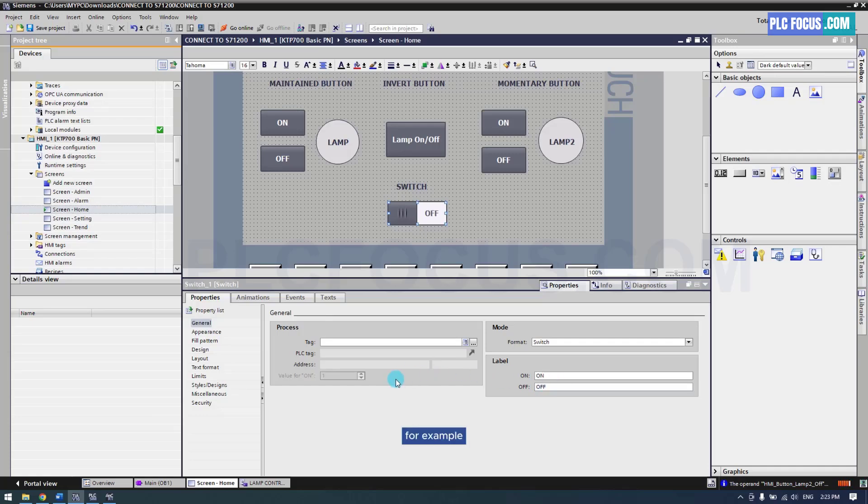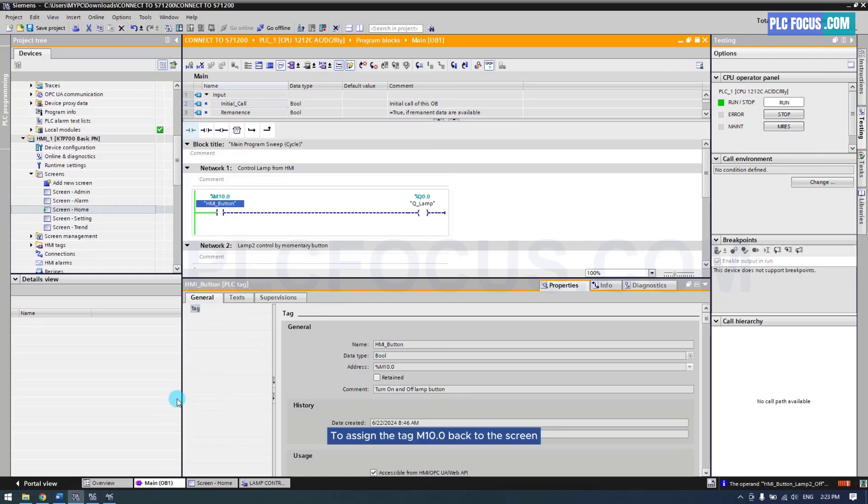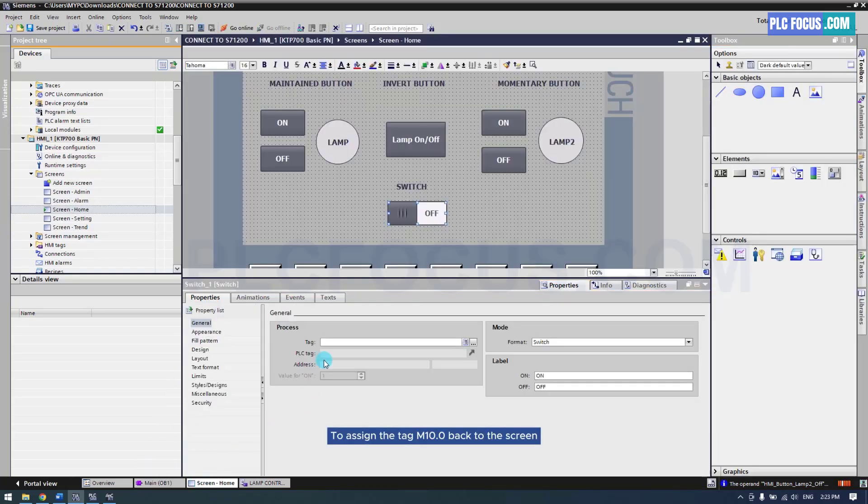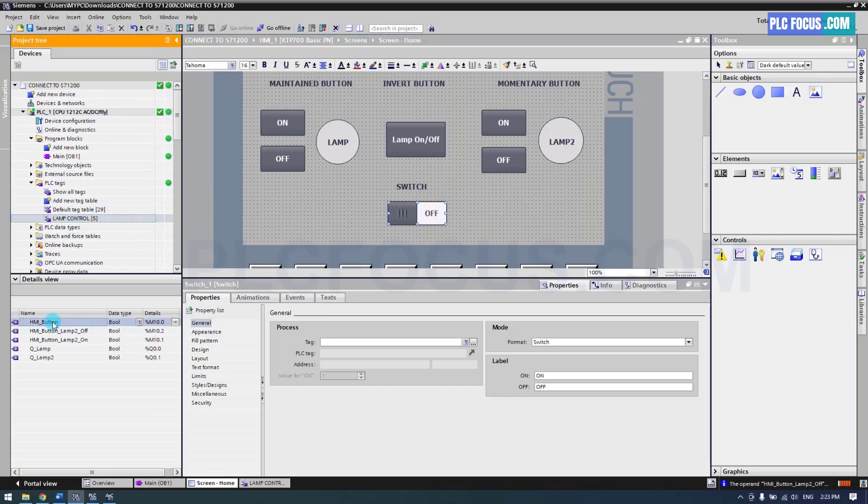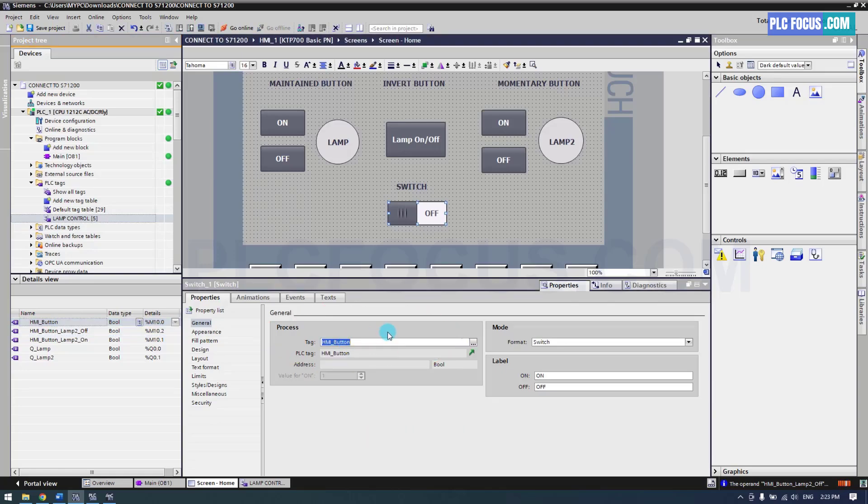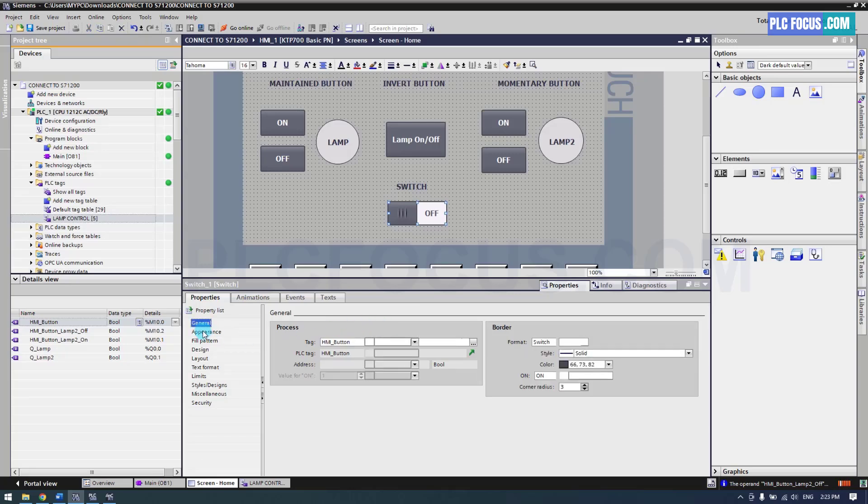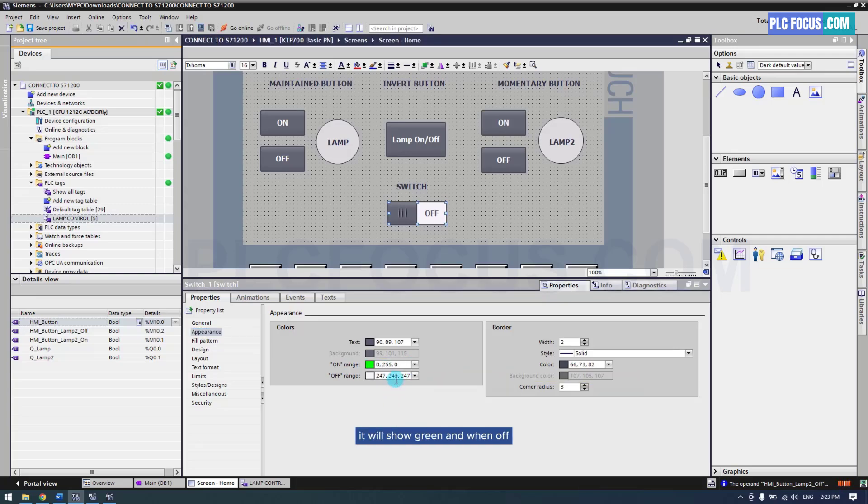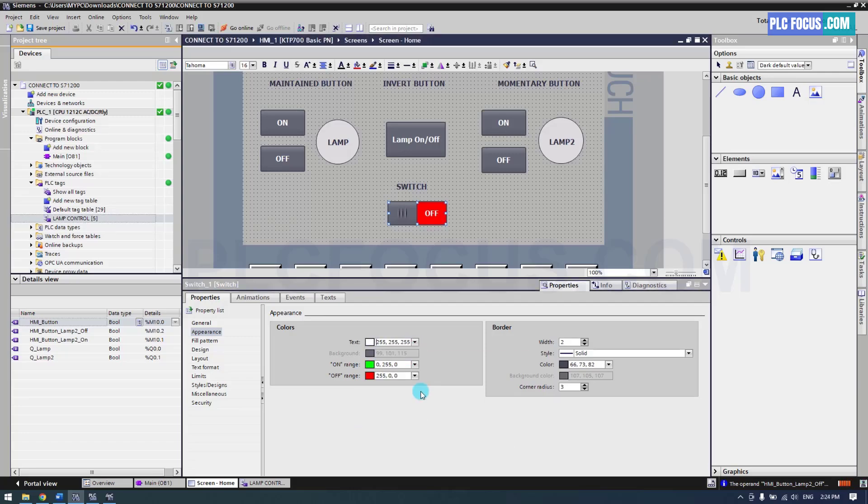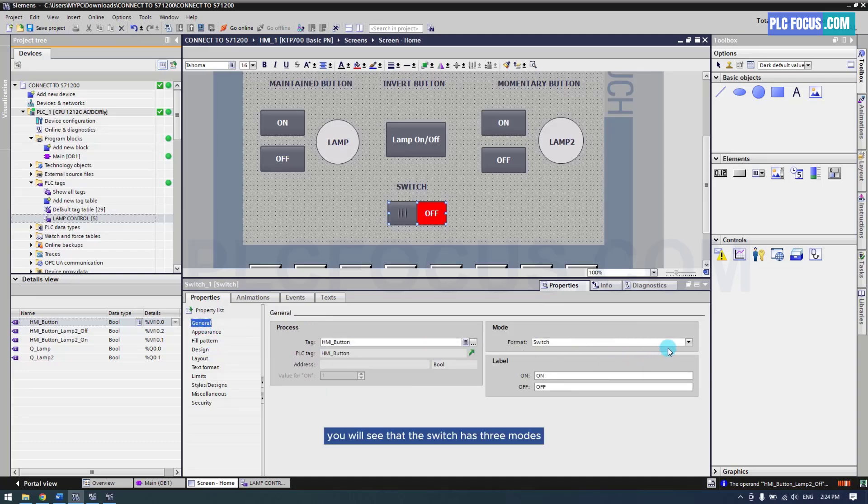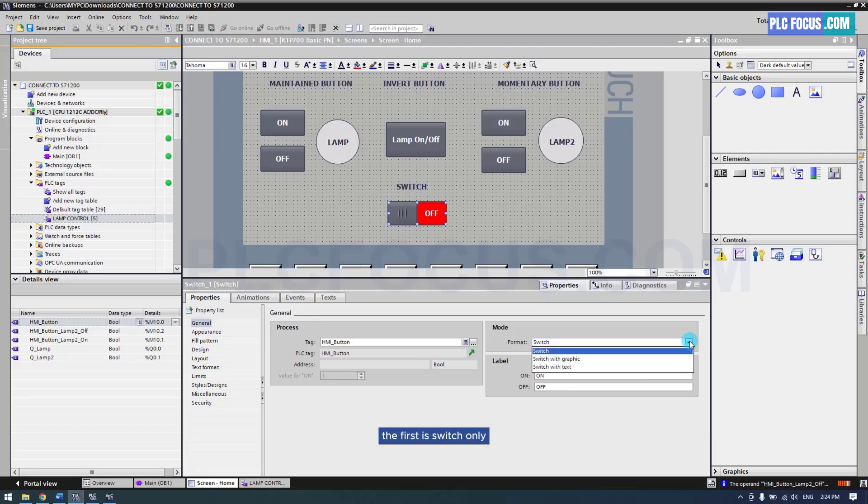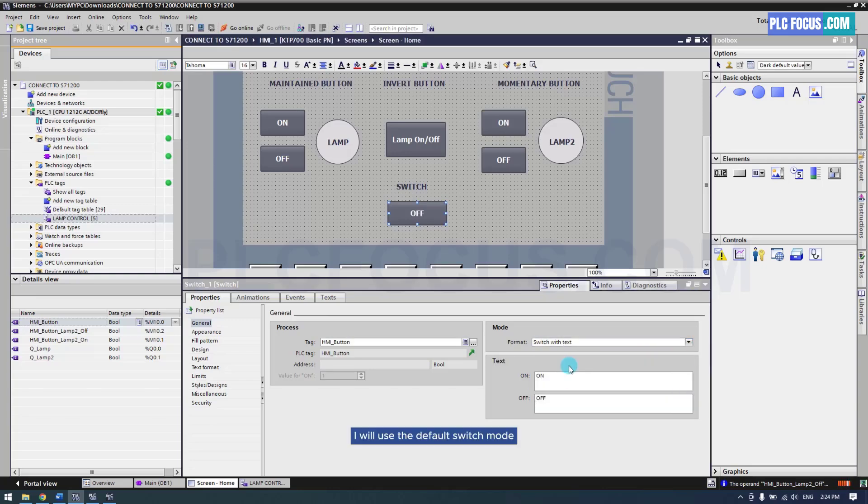For example, display the switch state according to tag M10.0. To assign the tag M10.0, back to the screen and drag the HMI button tag into the process tag property of the switch. You can also change the switch color. For example when on it will show green, and when off it will show red. Change the color of the switch. You will see that the switch has three modes. The first is switch only, the second is switch with an image, and the last is switch with text. I will use the default switch mode.